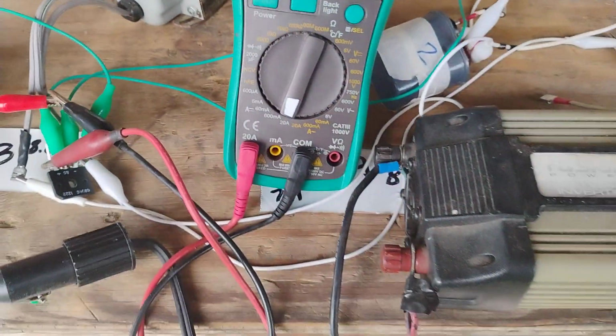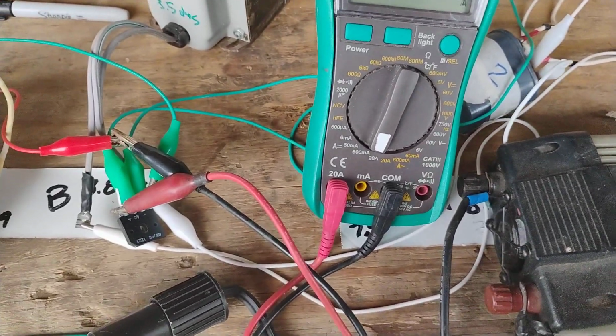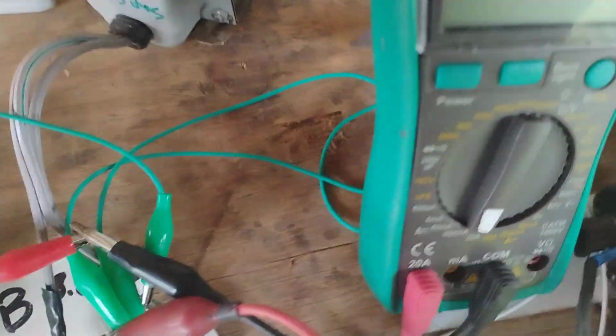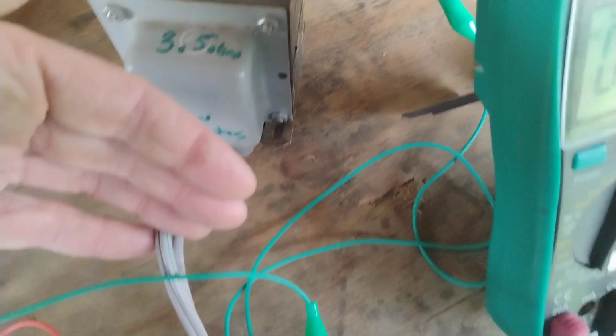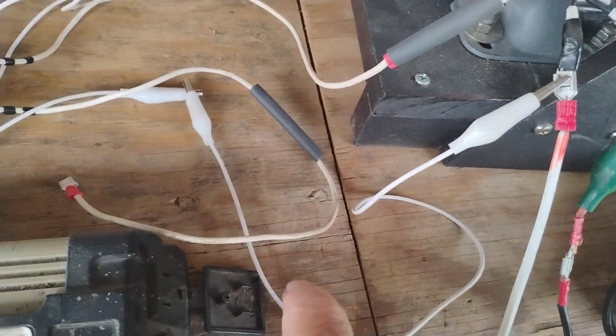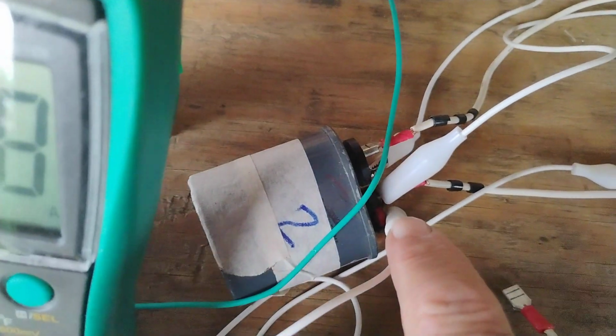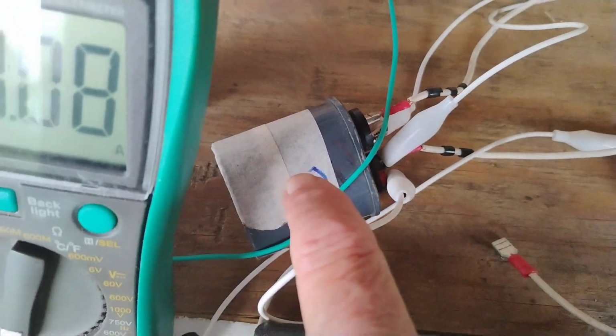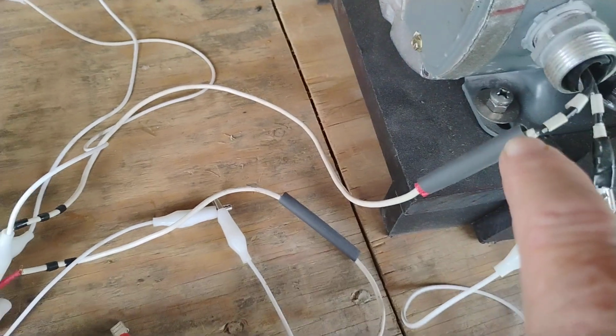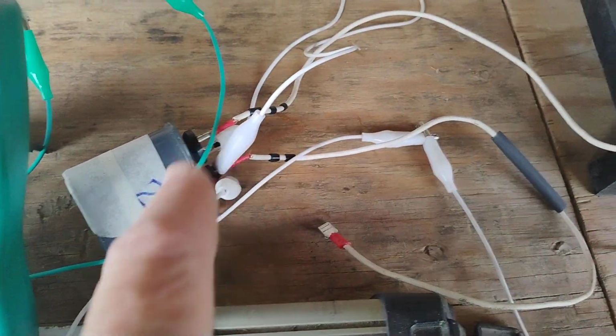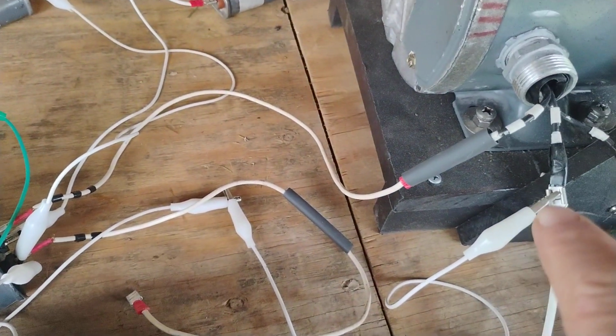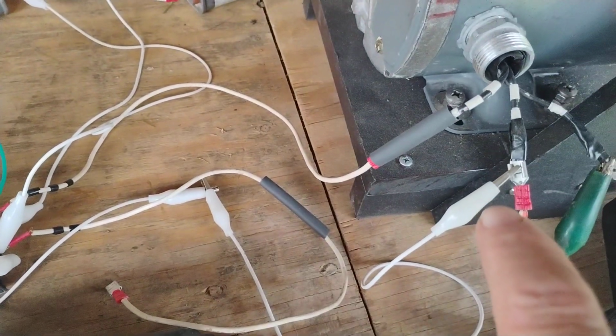And what it is, you take this transformer, you put it in series between the L2 line, and it goes to one side of this cap, the run cap, and the L3 line goes back to the motor. It's the basic rotoverter run cap phase setup.